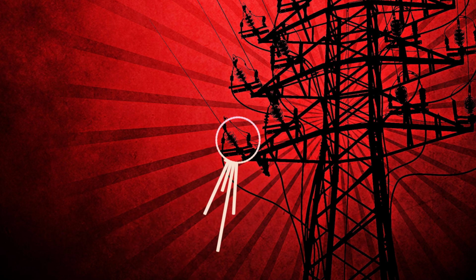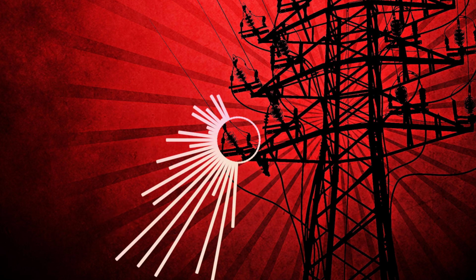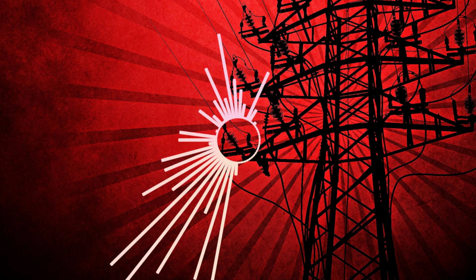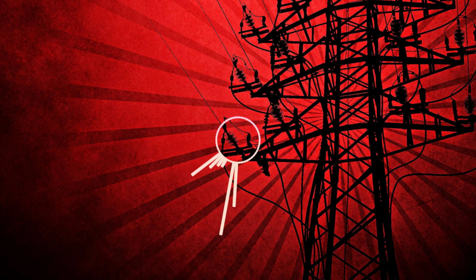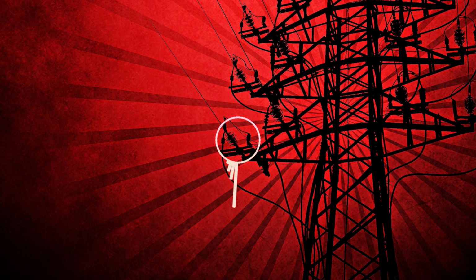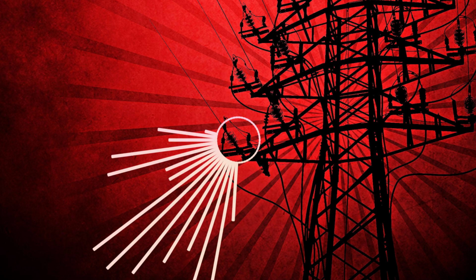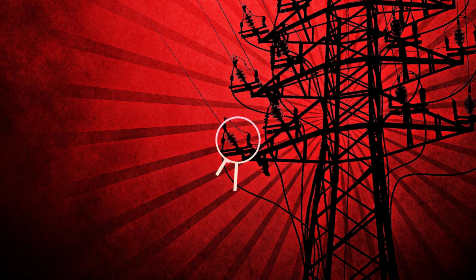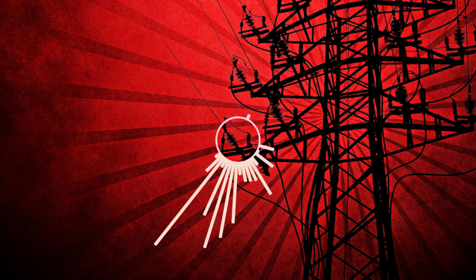Condition 3. Both sides are live. This is when electrical equipment is facing each other, both potentially energized. For example, two panelboards facing each other across a hallway in a room. The minimum depth in this situation is 4 feet or 48 inches. Basically, the higher the risk, the more space you need.